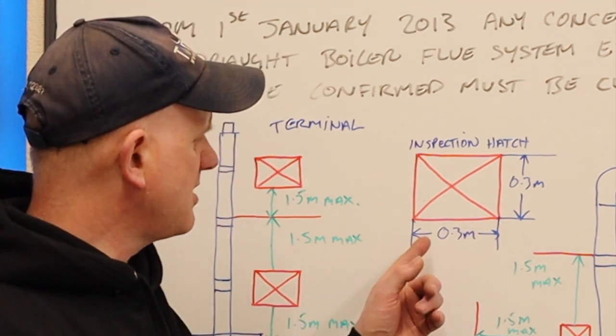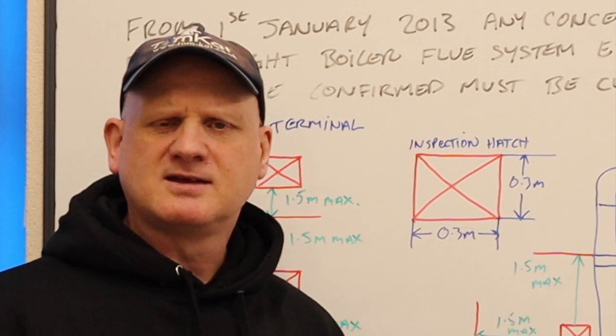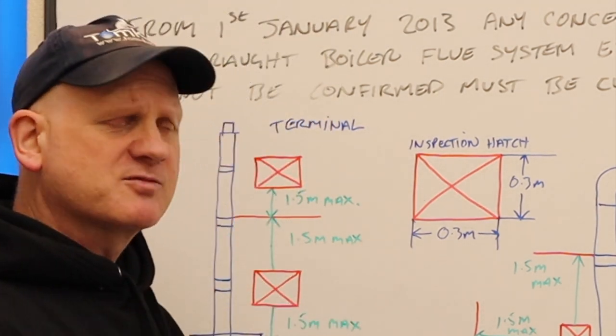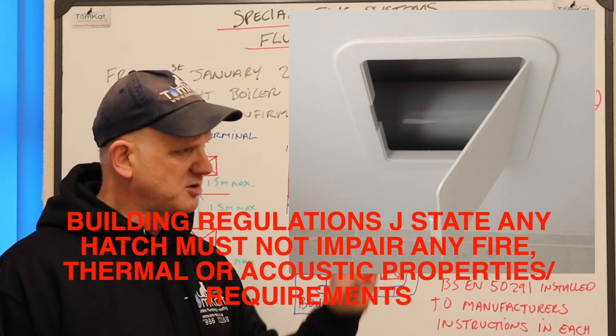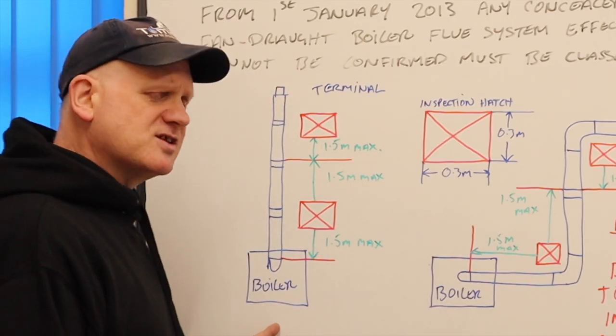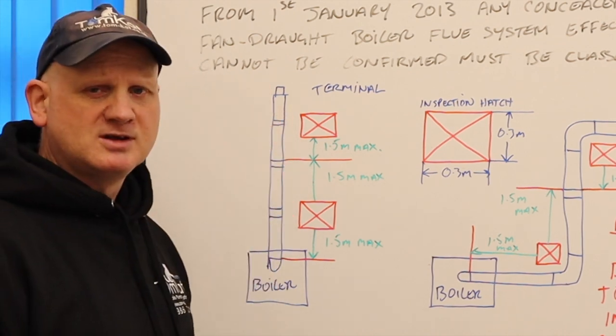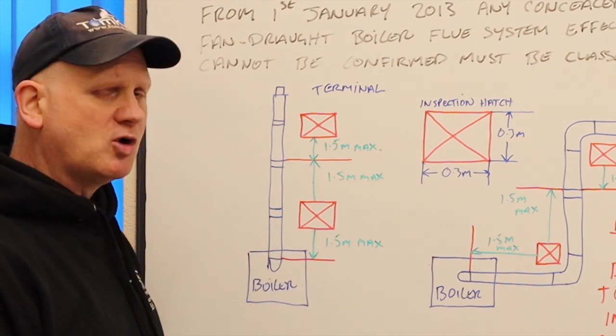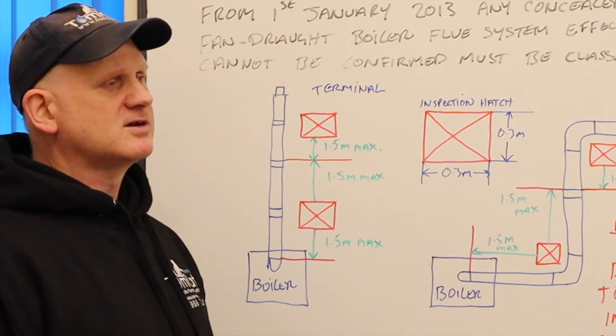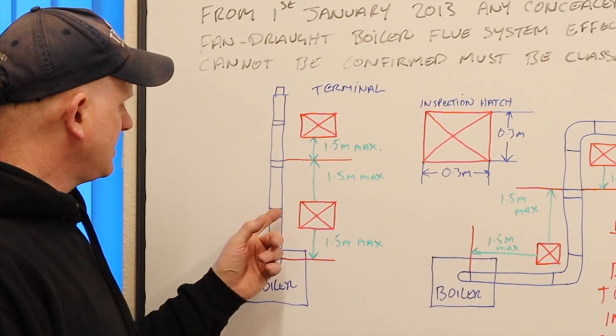To overcome flues in voids, we need to install inspection hatches. These must be a minimum of 300mm square so you can get your head through and have a look. They are specialist hatches — fireproof — so they maintain the integrity of the building. You can't just put a big hole in and cover it with a bit of plasterboard, and boxing with multiple screws that isn't easily removable doesn't count as an inspection hatch. These hatches must be no more than 1.5 meters away from a joint.